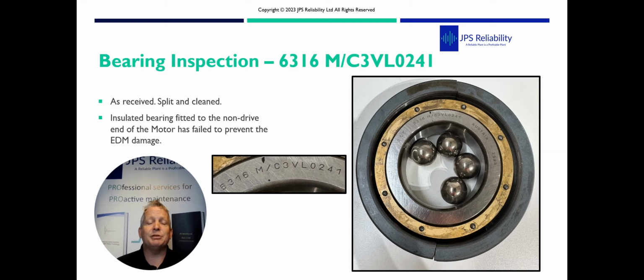So the bearing technically was still working, so it wasn't a functional failure. We pulled it before the bearing was a functional failure. And what we have found with EDM problems is they're not so uncommon now. They're more common because of the more drives people are installing to save energy. But you're not looking at the whole system, the cabling and the earthing, that it needs correct earthing for this high frequency current. And we've had two of the same motors on the platform off a drive, and they will behave differently, even down to when they're overhauled and put together and the spigots are put in.